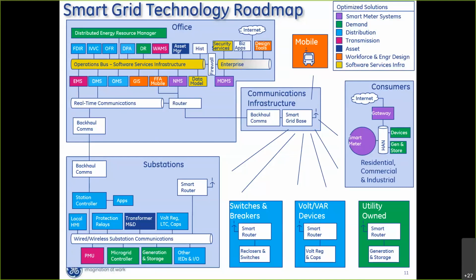Then to the right and the bottom, we see switches and breakers. We need switches on the feeders to support the fault detection, isolation, and restoration logic, and we need capacitor banks and voltage regulators on the feeders to support the integrated Volt/VAR control logic. Again, the logic could be at the control center or running in the substation. This is what I mean by a holistic solution—technology components from different vendors integrated together to successfully interoperate to meet the business needs of the utility.